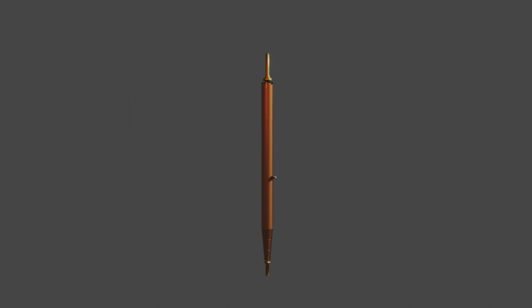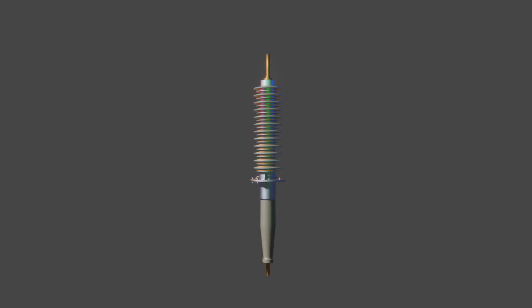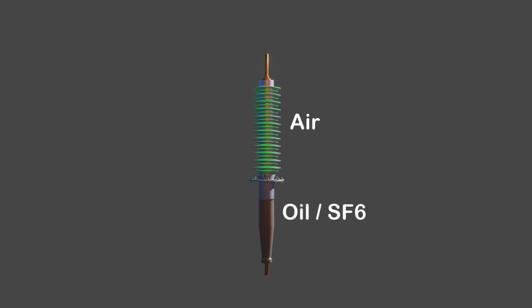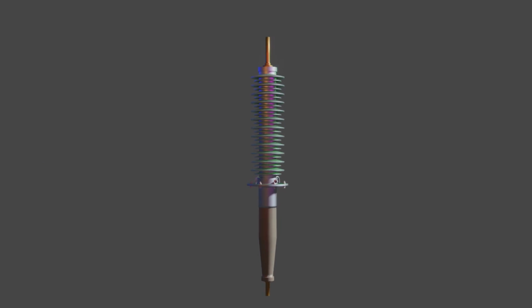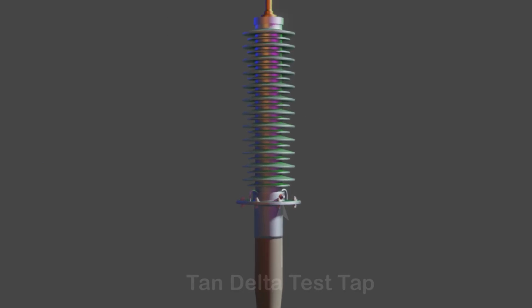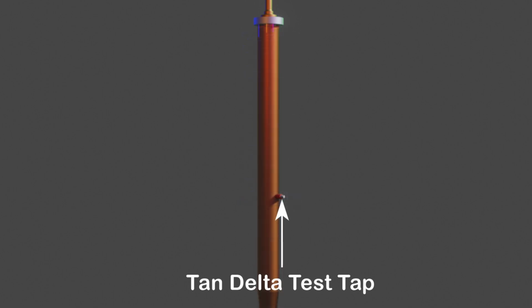Finally, the hardened core is placed inside the outer insulator housing and secured with a mounting flange at the bottom. The bottom flange is grounded to the transformer tank, often containing SF6 gas or oil, while the top protrudes into the outside air. You will notice a small test terminal called the tan delta test tap on the bushing. It is connected to one of the foil layers.